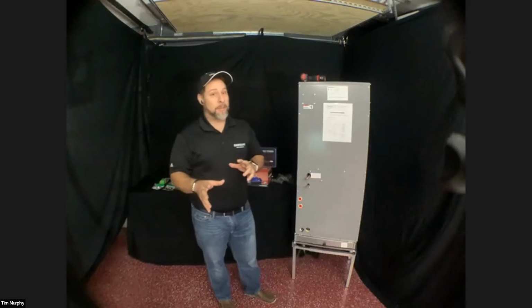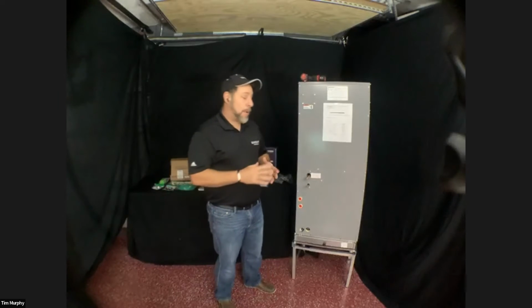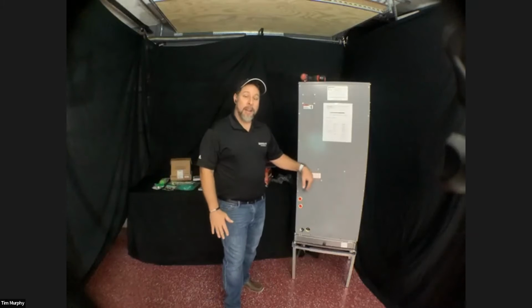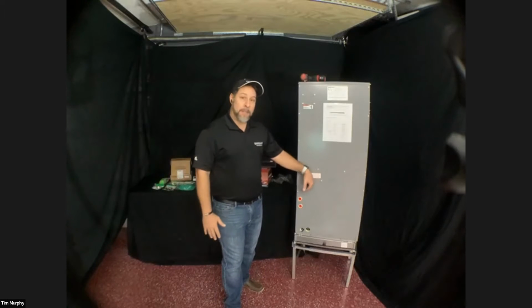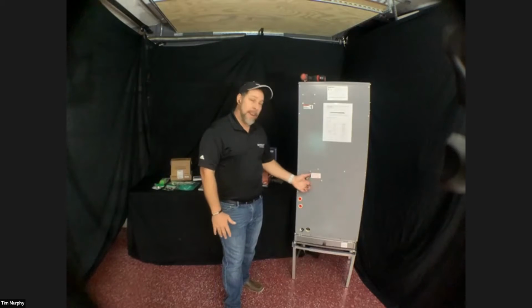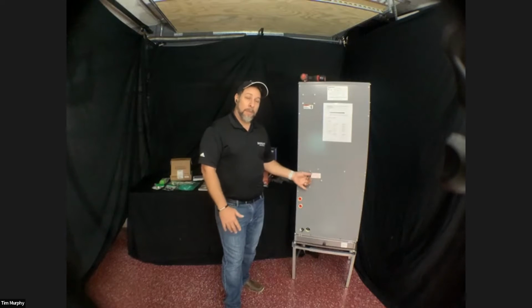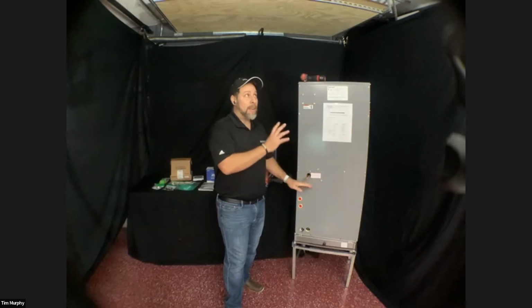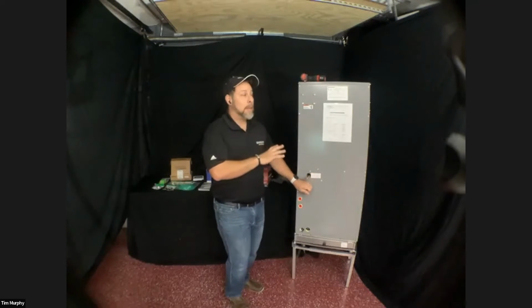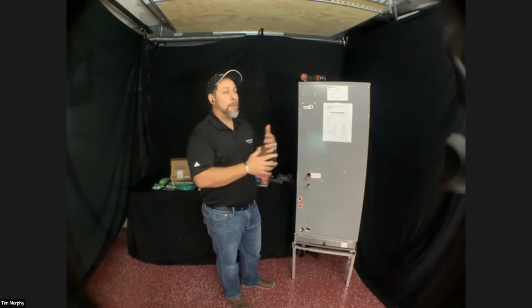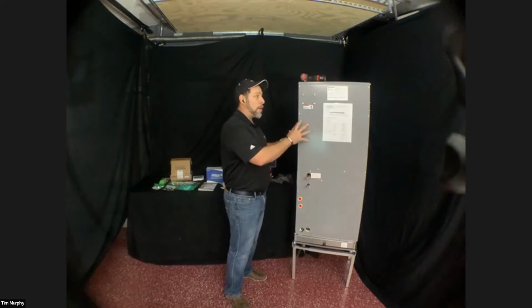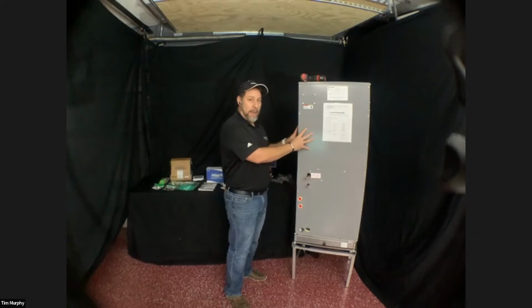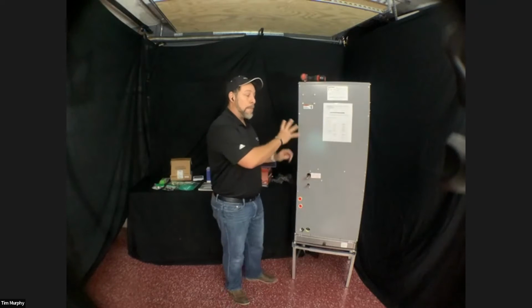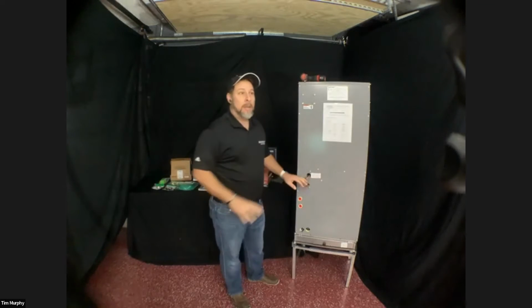Well, there's a couple reasons why that's important. One of the main reasons is because of your copper. You don't have the expansion valve in here, so what's going to happen? Well, both copper lines are going to sweat. So both copper lines are going to sweat. Herein lies maybe one of the hurdles if you're going from a conventional style AC system to a multi-position air handler.